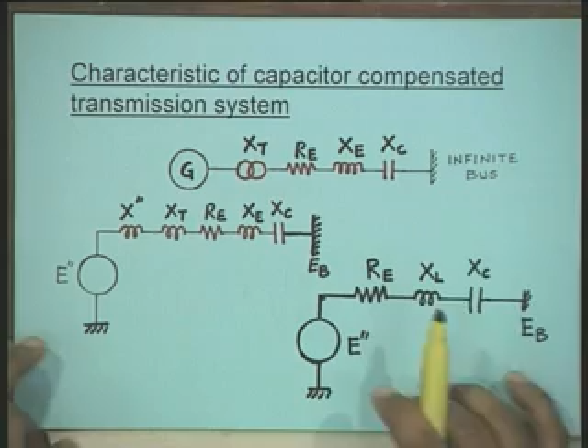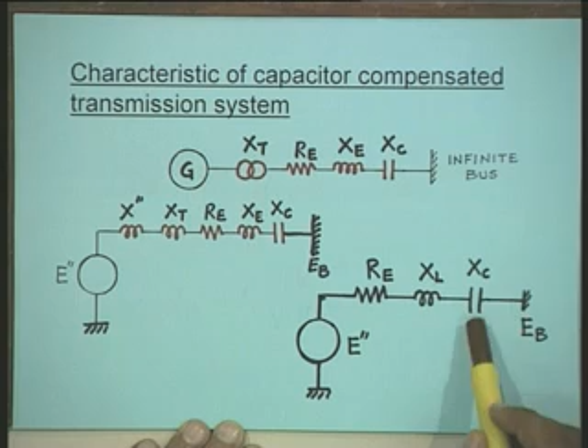Now, we can draw the equivalent circuit of the system: the generator is represented by a voltage in series with reactance, the transformer with reactance Xt, the line with resistance Re and reactance Xe, and the capacitance Xc. This can be simplified to a voltage source in series with the resistance, the total reactance XL, which is Xe plus Xt plus X double prime subtransient reactance, and a capacitance connected to the infinite bus. For this circuit, the natural frequency of oscillation, which we denote by omega n, is equal to 1 divided by the square root of LC.